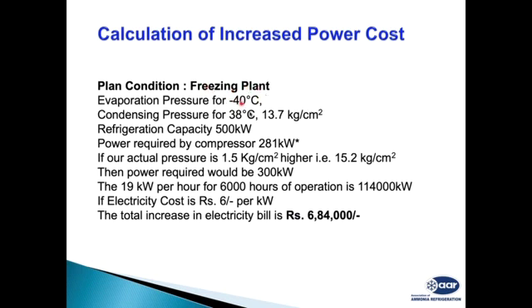Typically, a freezing plant operating at -40 evaporating and 38 degrees centigrade condensing, with 500 kilowatt refrigeration capacity, requires around 280 kilowatt of power. If our pressure is 1.5 kg higher, that is from 13.7 to 15.2 kg per square centimeter, then the power required will go from 281 kilowatt to 300 kilowatt to achieve the same refrigeration capacity. So this extra 19 kilowatt for 6,000 hours of operation in a year is around 114,000 kilowatt-hours. Considering the cost of power in India, which is around 6 rupees per kilowatt-hour, it will cost us around 6,85,000 Indian rupees. So you can consider the payback period can be almost less than a year.